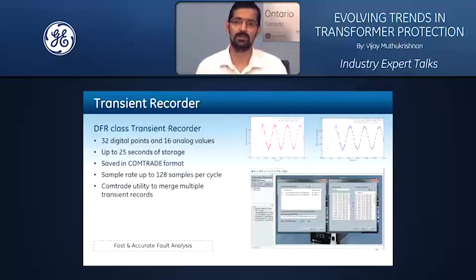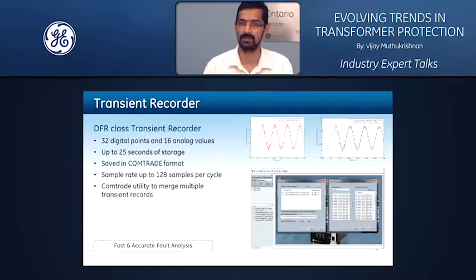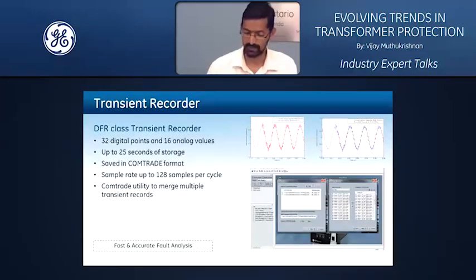Especially if you have a substation where a fault happened and the fault is seen by multiple relays, an ability to merge the COMTRADE files in a simple utility as part of the software program becomes very useful, because now you can grab data from multiple relays, combine them into a single COMTRADE file, time align them, and make sense out of the entire system phenomena, what happened in that particular fault condition. That is the power of the transient recorder functionality.